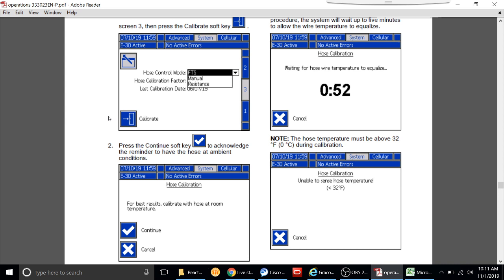So if I'm in the middle of a job and my FTS goes down, do I have to wait till it gets cold, or can I just do it right away? It's best to at least let it cool down a little bit and allow it to normalize. You can do it, it's just not going to be as accurate. Typically, in the morning, both sides, everything's at that same ambient condition. It's best to do the calibration then. All right, got it. So I'm going to hit the button that says continue. I'm going to start my calibration.